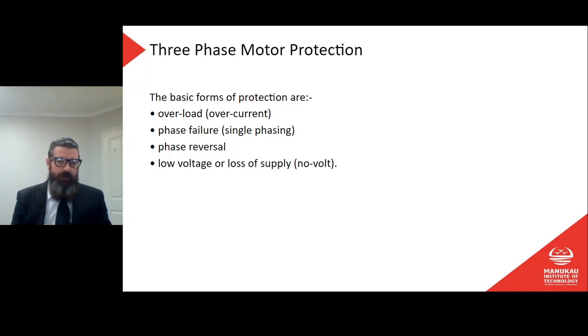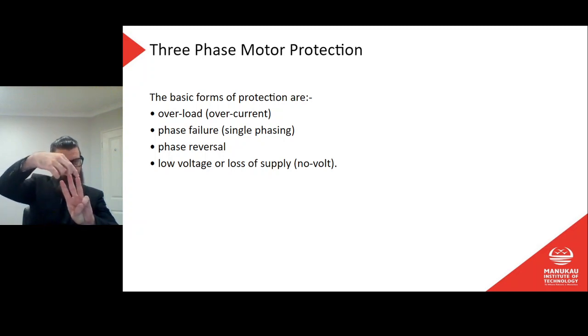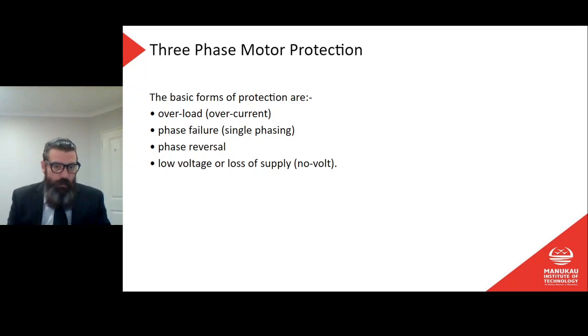Phase reversal, right, a three-phase motor. If we haven't talked about this before, then I can tell you now that if I have three phases, three lines, and they are connected to three terminals in a motor, and the motor turns, if I take any two of those phases and switch them over, could be these two, could be these two, could be these two, the motor will change direction. What? Neat, huh? So that's great. That's a really great tool that we can use. I can change the direction of any motor. I just change two of the wires. Cool. But we don't want that to happen accidentally.